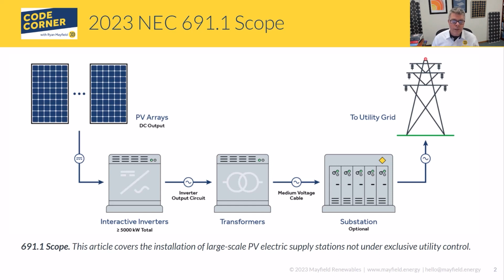The main point here is that the article is all about these large-scale PV systems that are not under the exclusive control of the utility. We often refer to these as systems behind the fence, meaning utility owned, utility operated. So these are systems that are not under utility control but are still large scale - independently owned and operated. If a system is under utility control, it follows their own specific codes, so it becomes outside the scope of the National Electrical Code. That's why we have that delineation that it's not under the control of the utility.